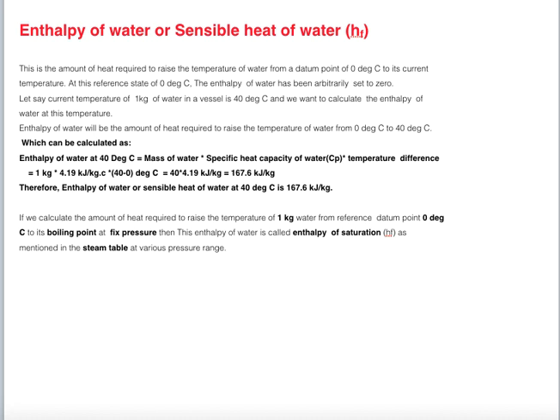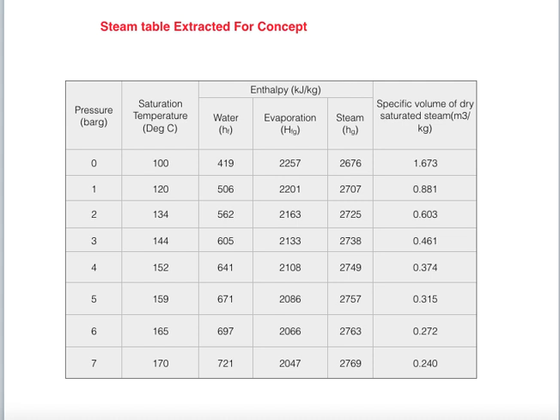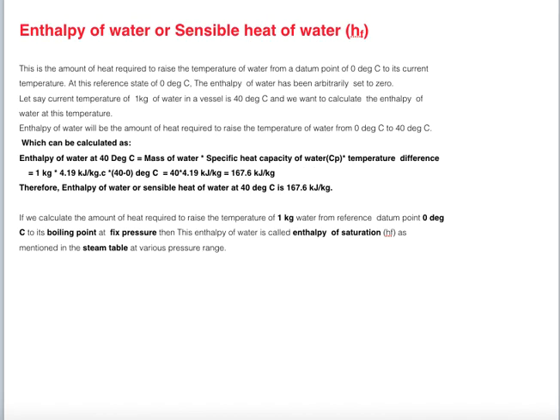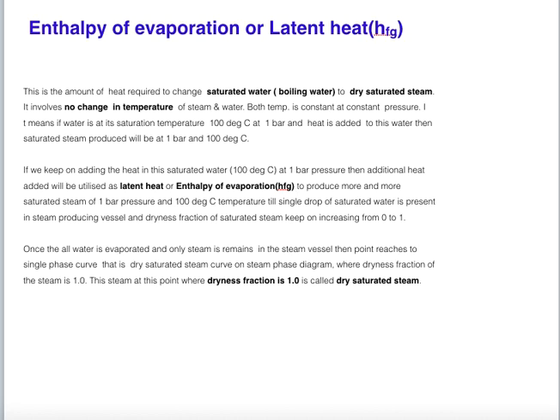If we calculate the amount of heat required to raise the temperature of 1 kg of water from the reference datum point of 0°C to its boiling point at fixed pressure, then the enthalpy of water is called the enthalpy of saturation, denoted by HF as mentioned in the steam table at various pressure ranges. From the steam table values shown, we can see that the enthalpy of saturation of water increases as pressure increases.